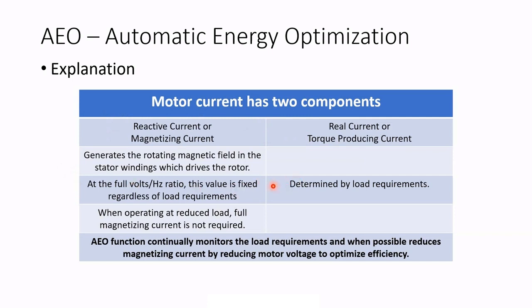The torque-producing current is dependent on the load and produces enough torque to drive the motor. When operating at reduced load, full magnetizing current is not required. That's going to happen frequently with fans and pumps — they're designed to run at reduced speed and will certainly be at reduced load, and also with dampers and valves closed. The AEO function continually monitors the load requirements and, when possible, reduces the magnetizing current by reducing motor voltage to optimize efficiency.